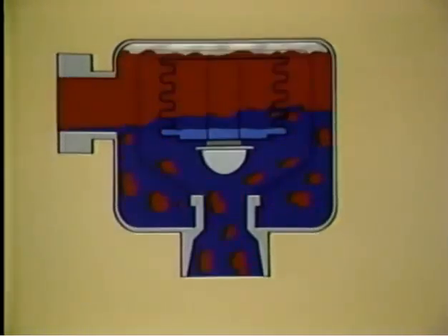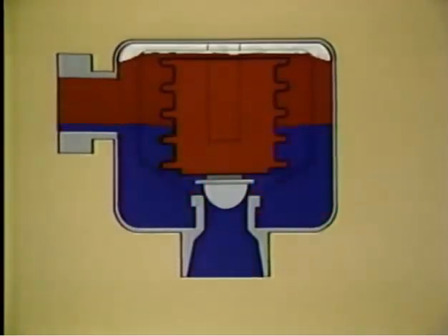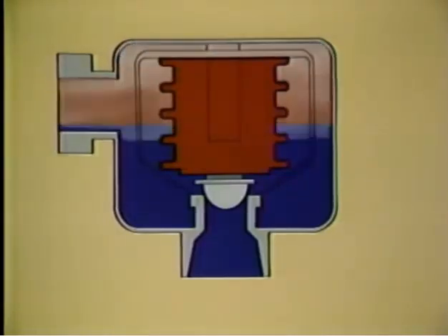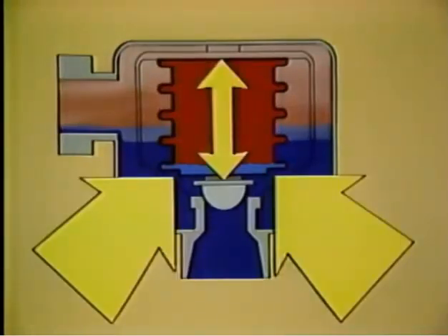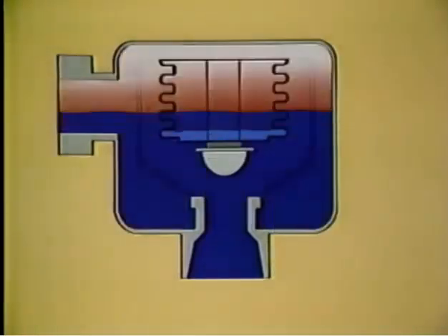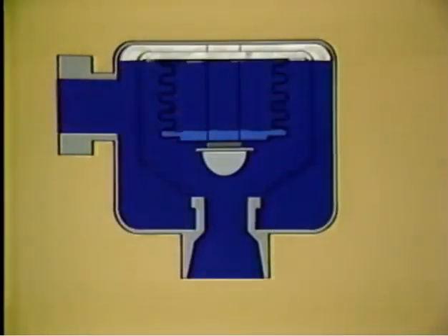When the fluids and gases inside the trap reach sufficient temperature, the trap once again closes. Air and other non-condensables mixed with the steam also lower the temperature inside the trap. When the surrounding temperature falls below the saturation point of steam, the charge begins to condense. With greater pressure outside than inside the bellows, it compresses, pulling the valve off the seat.